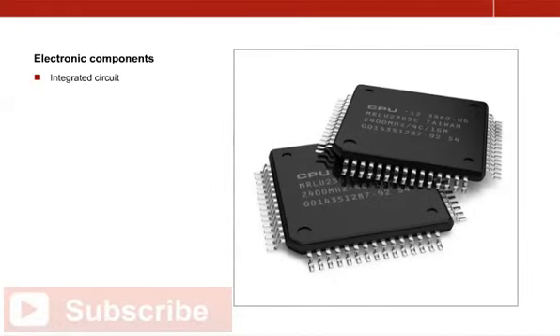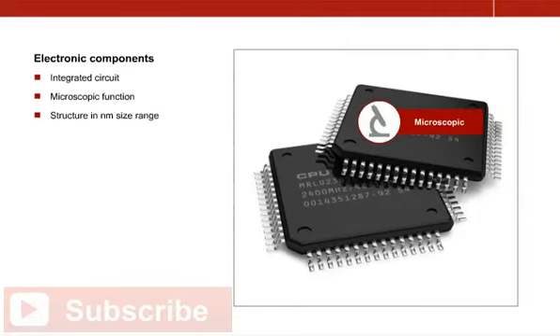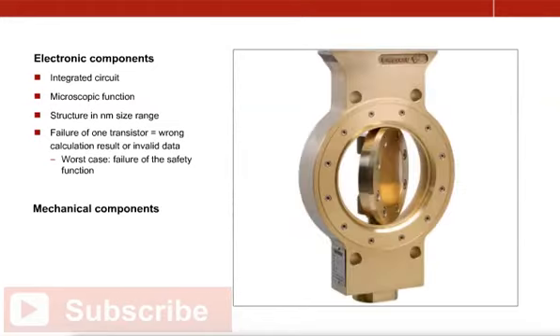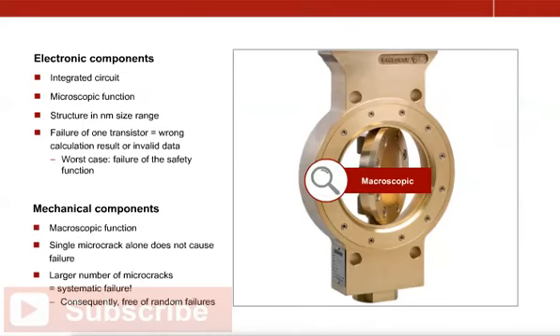Random faults in technical equipment result from malfunctions in the microscopic range. As a result, they can neither be predicted nor prevented. They are of particular importance in electronic components, such as integrated circuits. The function of a microprocessor or a memory chip is performed by structures in the nanometer range, that is, clearly in microscopic dimensions only slightly above the atomic level. If only one in a billion transistors fails, it inevitably leads to a processing error, and in the worst case, causes the safety function to fail. In mechanical components, individual anomalies in the microscopic range are harmless, since they do not weaken the overall structure. If such anomalies occur with increasing frequency, however, they indicate a problem in the manufacturing process, and are thus considered systematic failures.